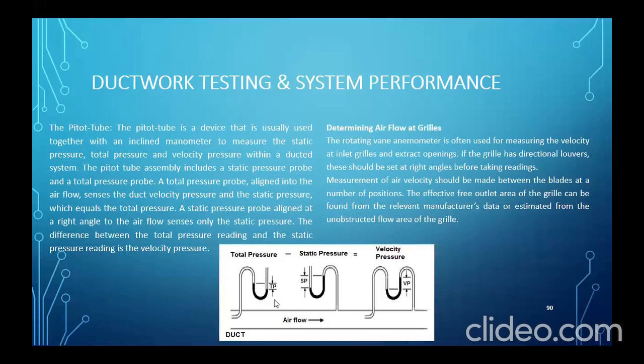This is used for ductworks. Di ba? Tutusukin mo yung ducting. So now, for the airflow at grills, the rotating vane anemometer is often used for measuring the velocity at inlet grilles and extract openings. If the grill has directional louvers, they should be set at right angles before taking the readings. Yung grills kasi open, hindi naman siya diffuser. So pwede mo siyang direktahin yung instrument na anemometer.